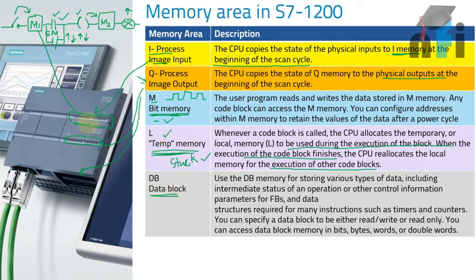Then you have data blocks. Suppose my input is connected to a sensor that reads the number of blocks, boxes, or bottles. I want to store that information in my PLC — I will use data blocks. Data blocks can generally be displayed on your HMI or touchscreen. For example, you can count how many bottles are coming, how many boxes are going — that information is stored in special memory known as a data block.